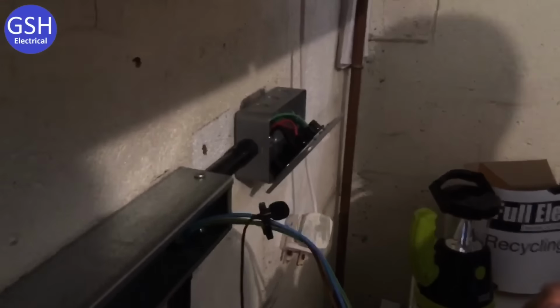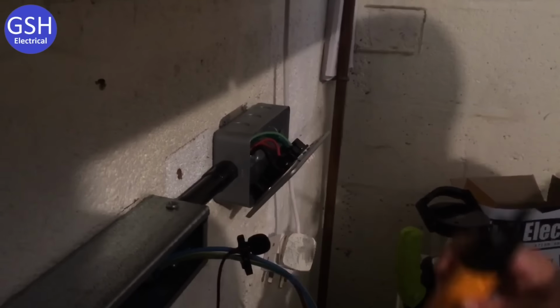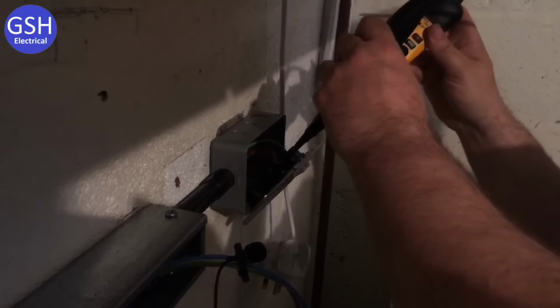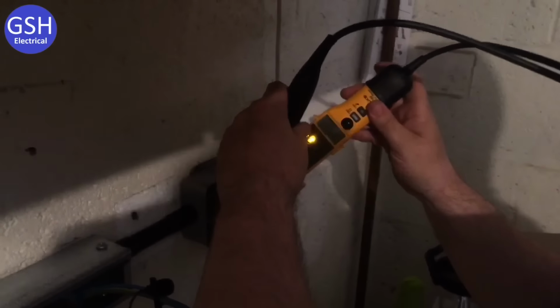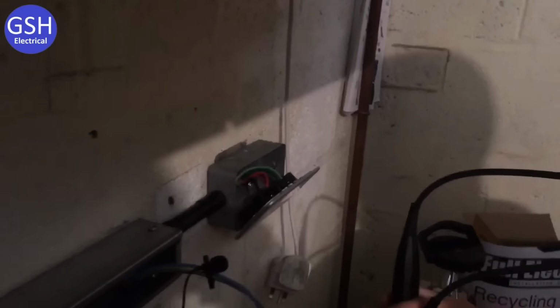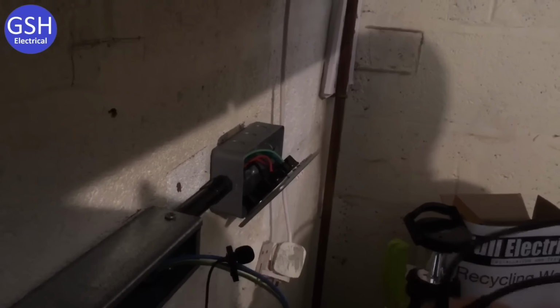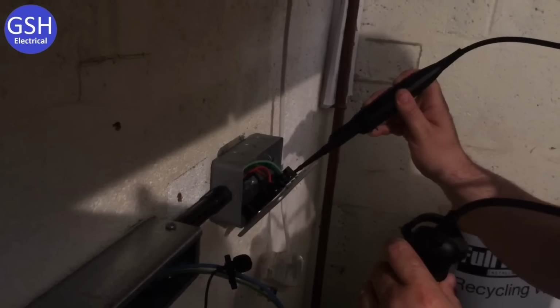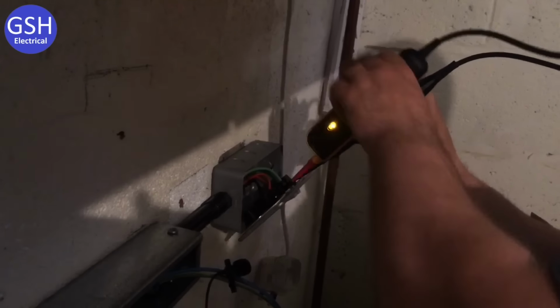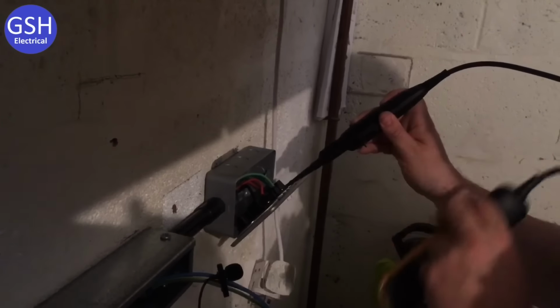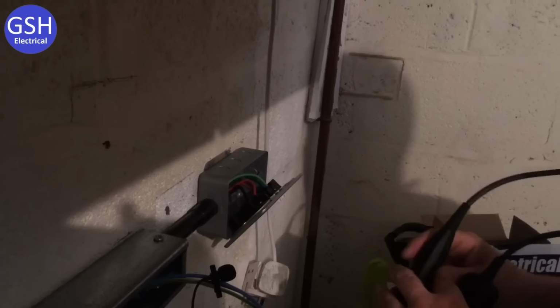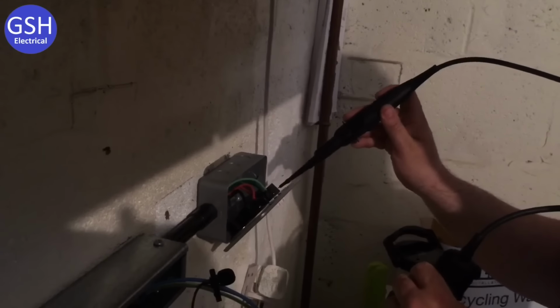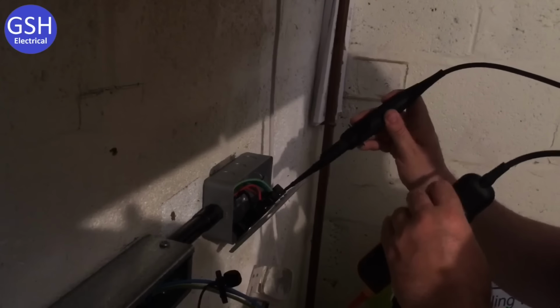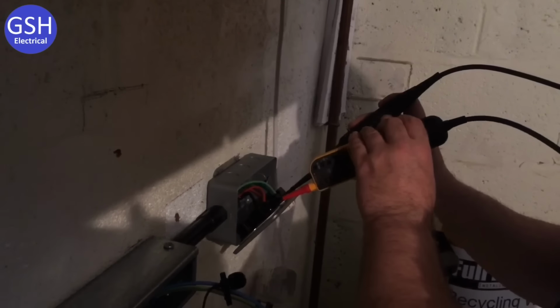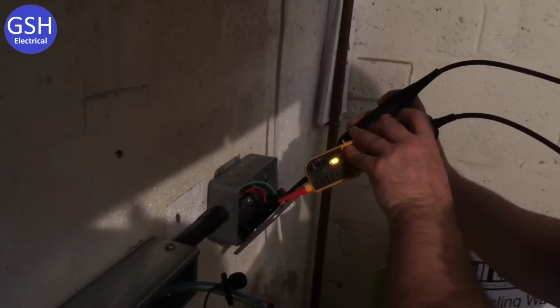Okay, so now I'm going to probe between line and neutral. I'm going to probe onto the neutral first, and then onto line, and that's dead. Then I'm going to probe onto the CPC and line. Which one are you coming off first? Off the line first. And then I'm going to do between CPC, I'm going on there first, and neutral, and come off neutral first and then CPC. Brilliant. What are you going to do now?